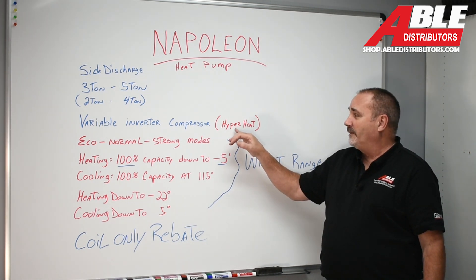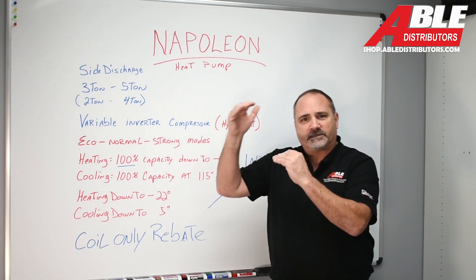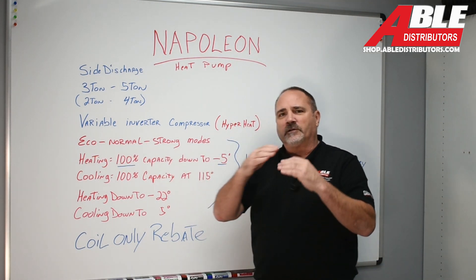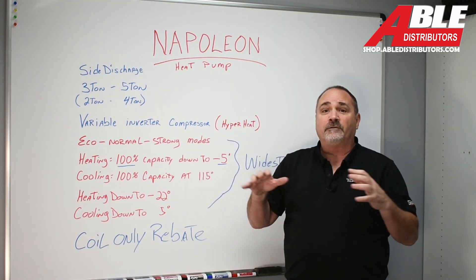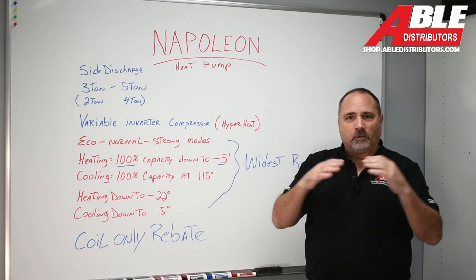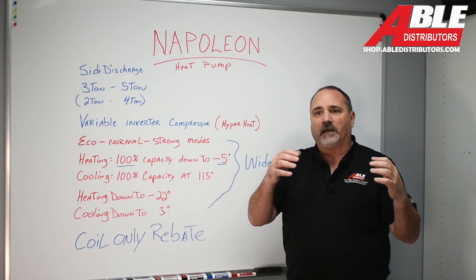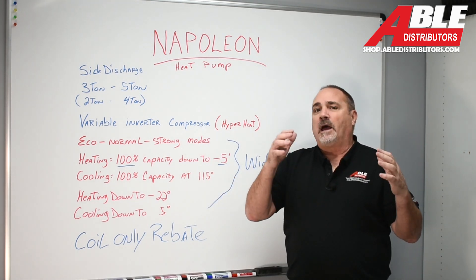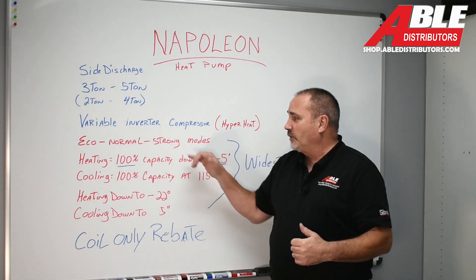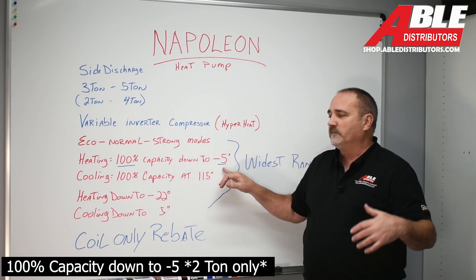Variable inverter compressor, hyperheat — we're going to get to that in a minute, but that says it all. This one has three modes, which are a little different than Bosch. Bosch has normal and accelerated; these change the way it modulates. There's eco mode — the slowest moving — and if that works for you, that's the best setting to save energy. It comes set in normal mode, and then it has a strong mode — great for a unicoil application.